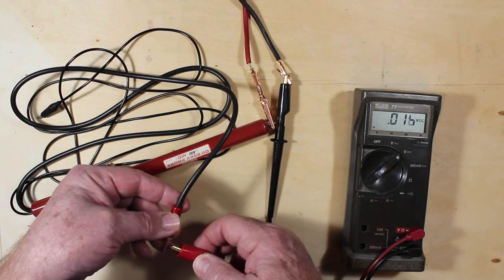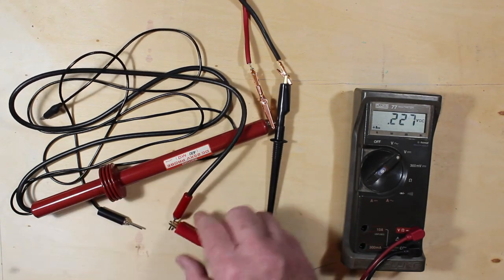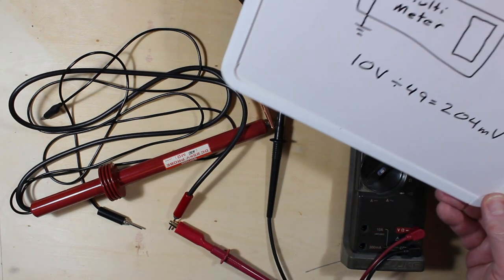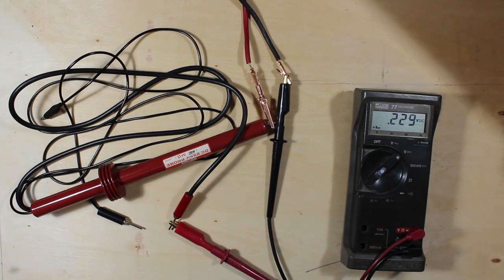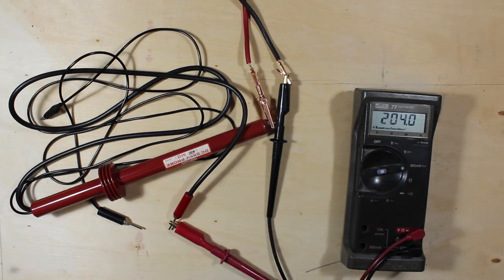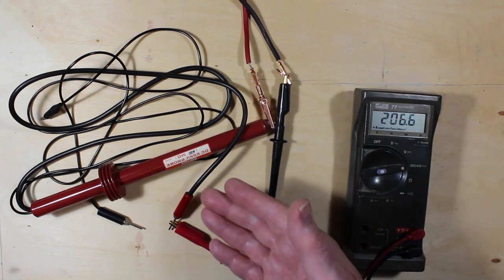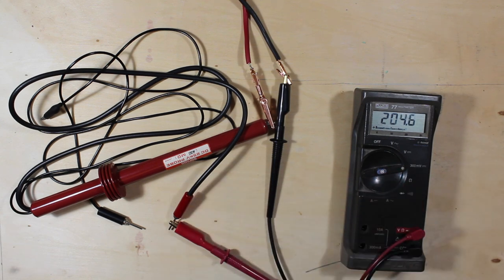So we're going through the 49, and we were looking for about 204 millivolts. And if I turn this down to the 300 millivolts scale to get better accuracy, we can see we're at 206. Pretty close, that's not a bad reading there. We're within a couple of percent.